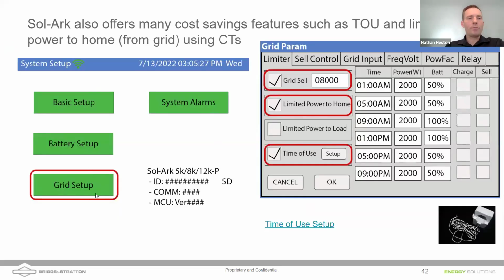Under grid setup, after you finish programming the battery setup, you can set up the grid setup in the inverter. There are a number of nice features. We don't have time to get into all of the things like time of use, but I've linked a nice video for you about how to do time of use settings. There are different limitations that you can do. You can sell back to grid. You can use limited power to the home, which is also a common feature. If you use limited power to the home, you can use CTs to limit the amount of power you're drawing from the grid and produce more of that from your batteries.